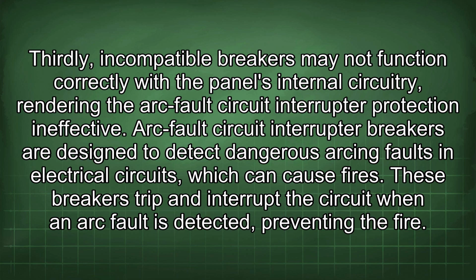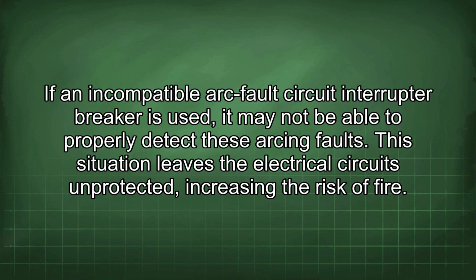Arc fault circuit interrupter breakers are designed to detect dangerous arcing faults in electrical circuits, which can cause fires. These breakers trip and interrupt the circuit when an arc fault is detected, preventing the fire. If an incompatible arc fault circuit interrupter breaker is used, it may not be able to properly detect these arcing faults. This situation leaves the electrical circuits unprotected, increasing the risk of fire.